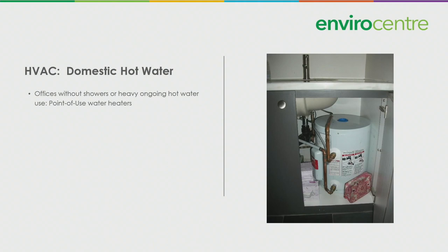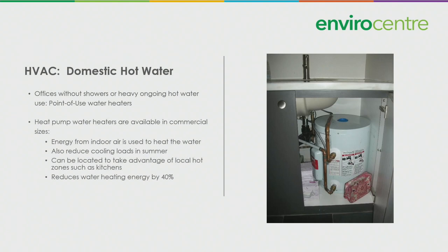If you do happen to have showers, then you would want to think about installing heat pump water heaters. They are available now in commercial sizes. They take energy from the indoor air and they use that to heat the water. They can also reduce your cooling loads in summer because they're actually going to be cooling the air inside. They can be located to take advantage of local hot zones such as kitchens. And they will reduce your water heating energy by 40%. You can also add drain water heat recovery units for about a 15% reduction.